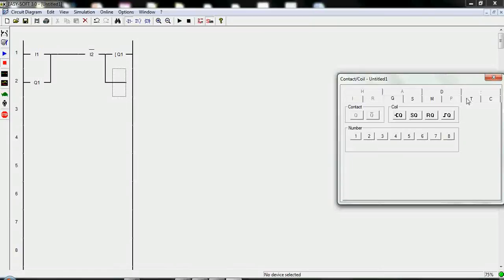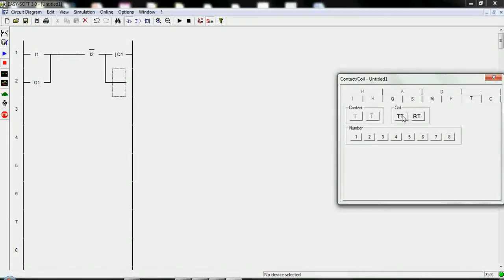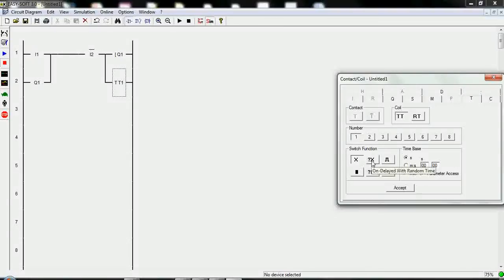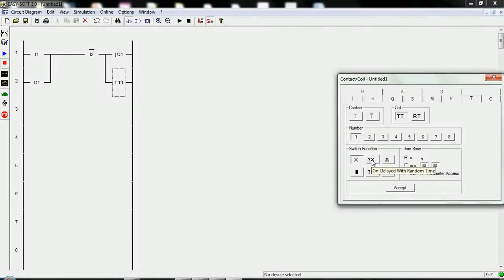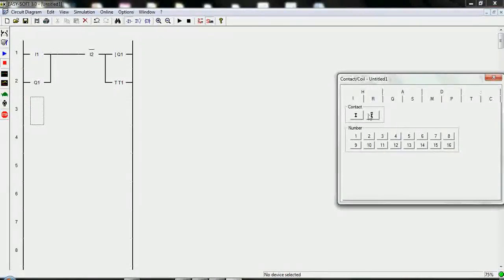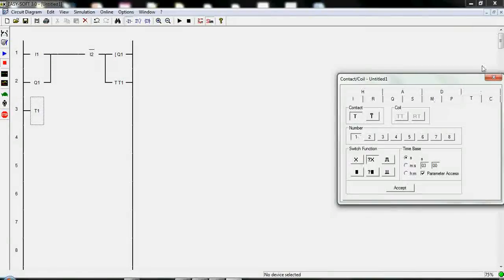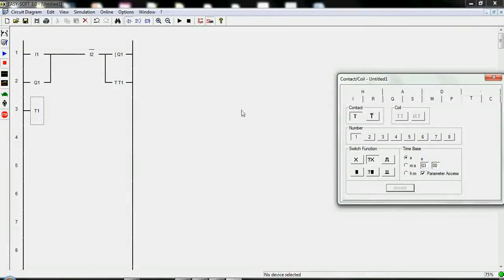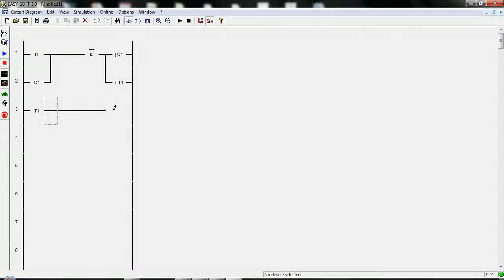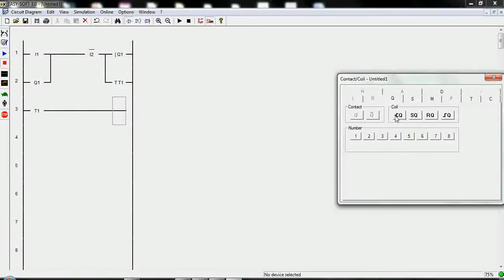Let's add timer situated here, TT1. And on-delay we illustrated why we need on-delay with random timer. On-delay with random time is one of the important ones. It's just on-delay timer but works in a random time. Sometimes it gives three seconds as we illustrated here. Sometimes it will give after two seconds. In some cases it gives one second.